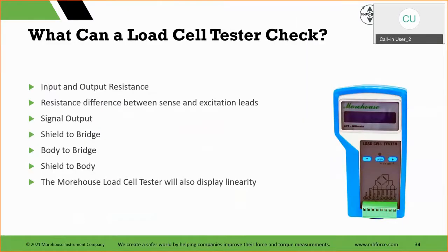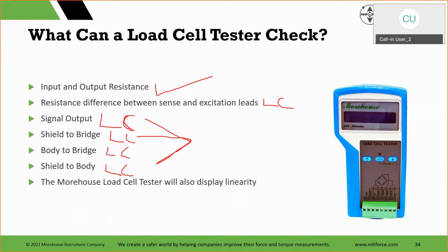Input and output resistance. That one you can do with a $20 handheld multimeter. That's load cell tester, doesn't give you much over the meter there. Resistance difference between sense and excitation leads. That's a lot more difficult to do on your handheld, so this would be a win for the load cell tester. Signal output, that's zero balance. It'll tell you that. That's a win. Shield to bridge, again, that's load cell body to bridge, shield to body. These are things a lot of people throw out. All these 3 things here.